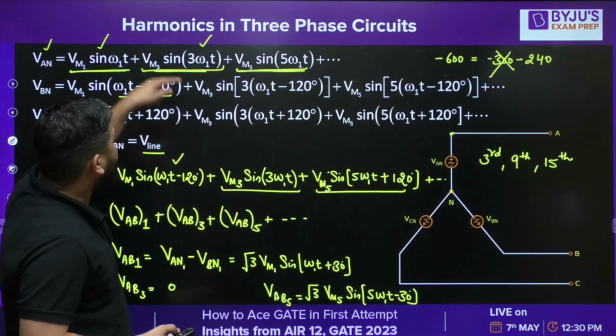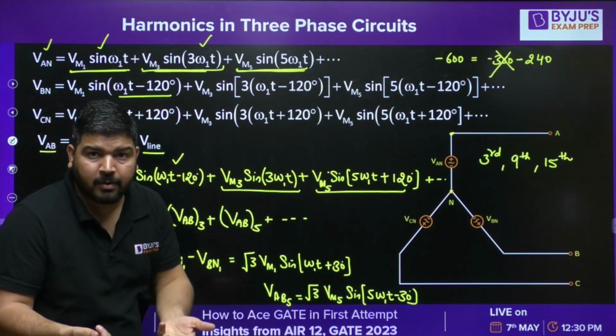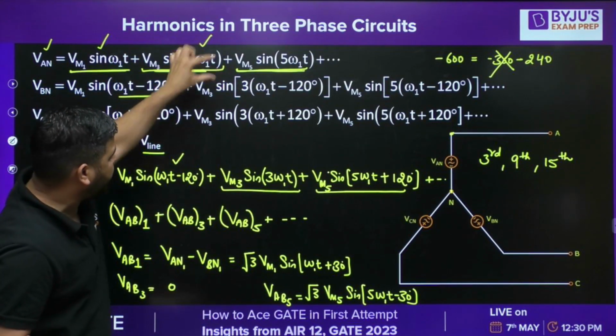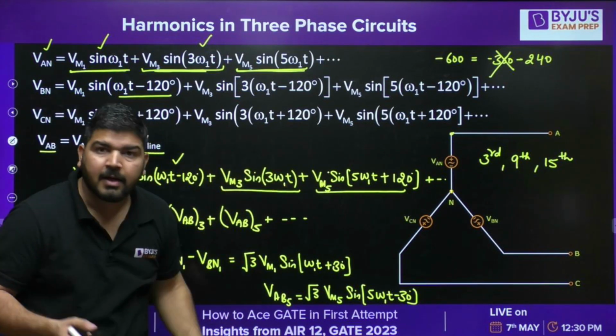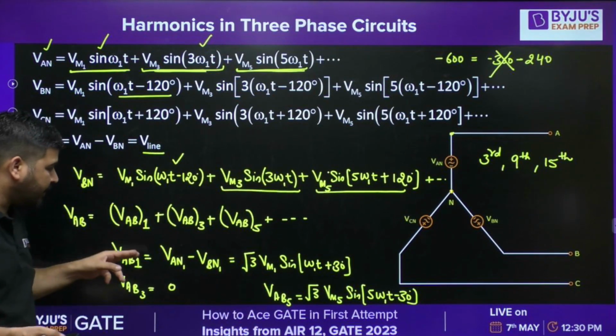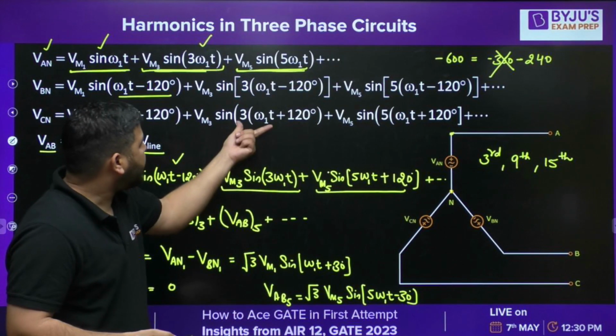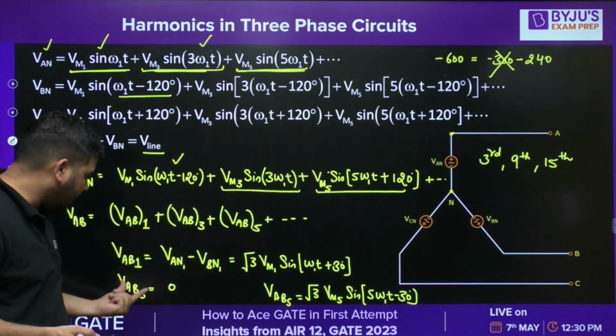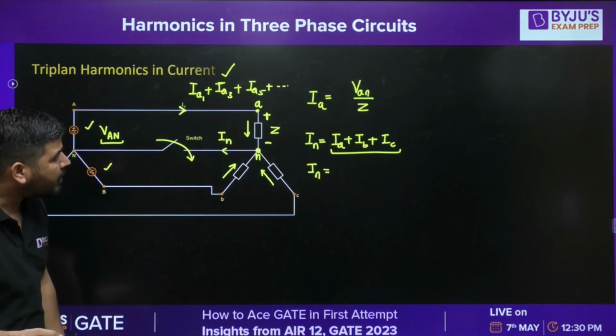I've already told you, look at the voltage - the same behavior occurs. The triplen harmonic voltage in phase A and phase B are in the same phase, so if you take the difference, they will cancel - the third harmonic will cancel. But here, in the neutral current, you are not taking the difference, you are adding.